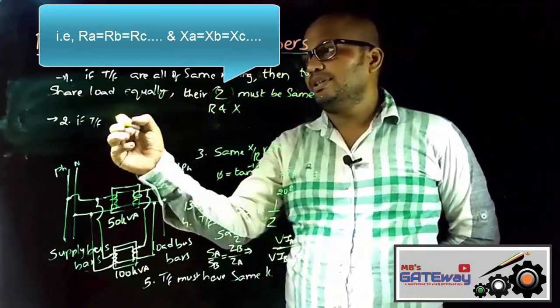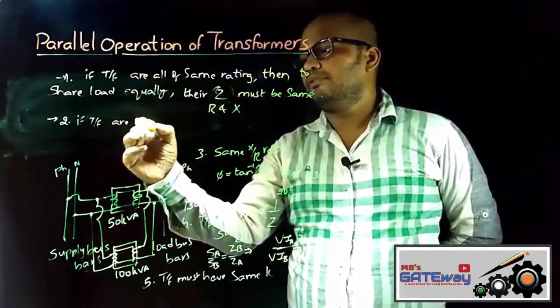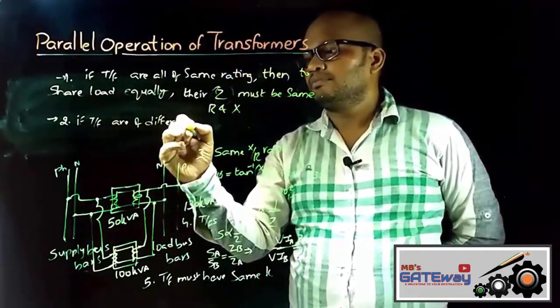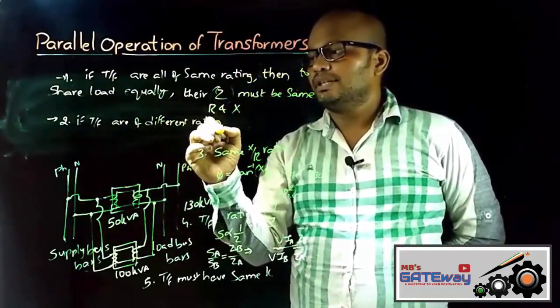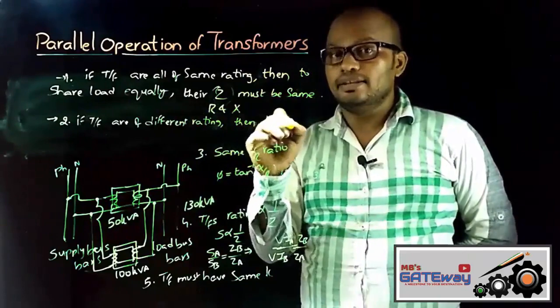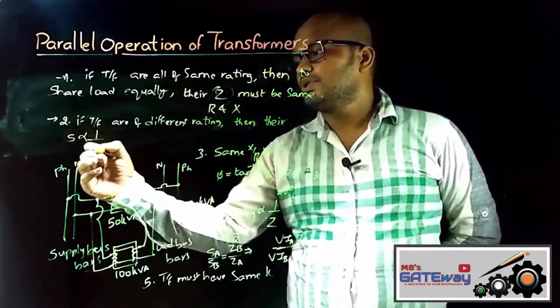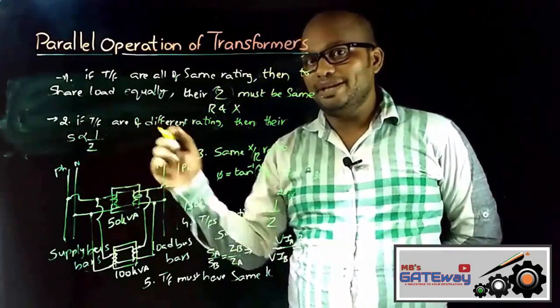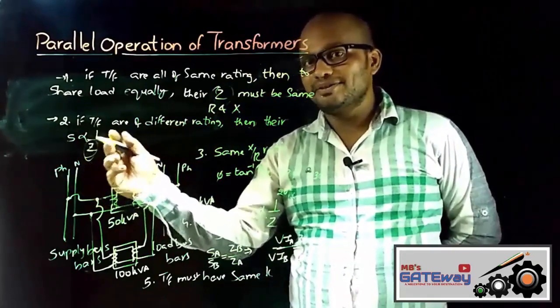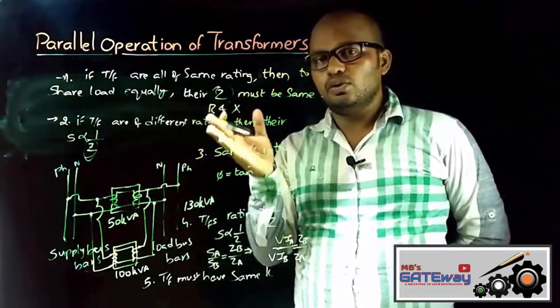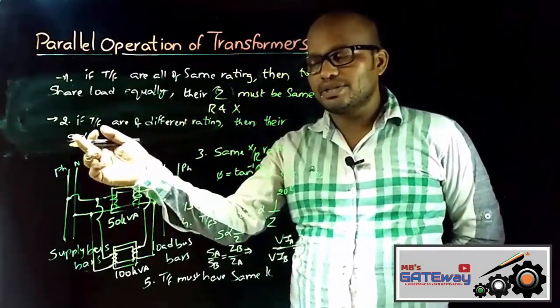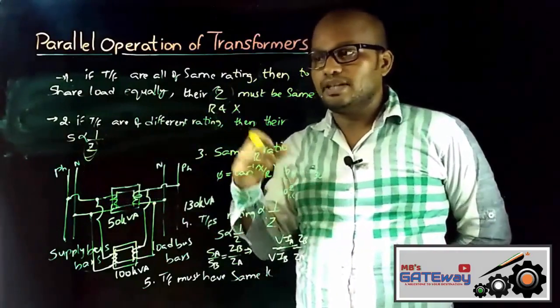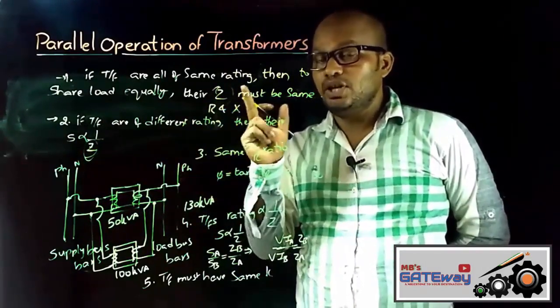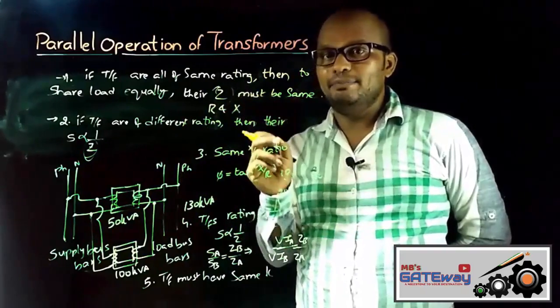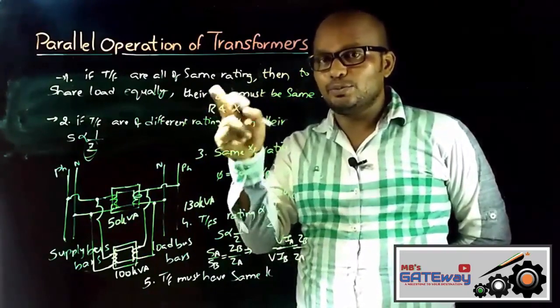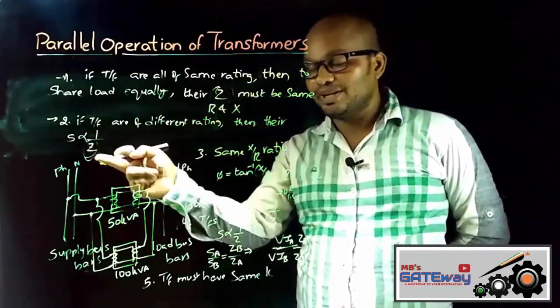And the second point is, if transformers of different ratings are in parallel operation, then their ratings must be inversely proportional to their respective impedances. And here impedance is a numerical value. That is, to share the load in equal proportion, a high rating transformer must have low impedance. And you must understand this big difference between the numerical value and impedance. Here it is not numerical equality, and here it is numerical equality.